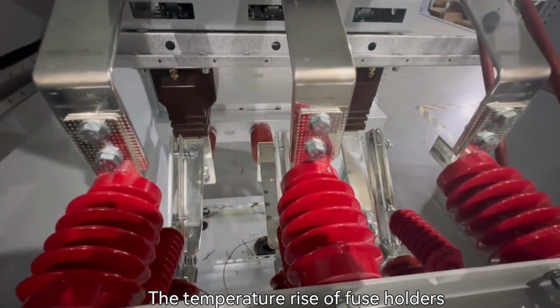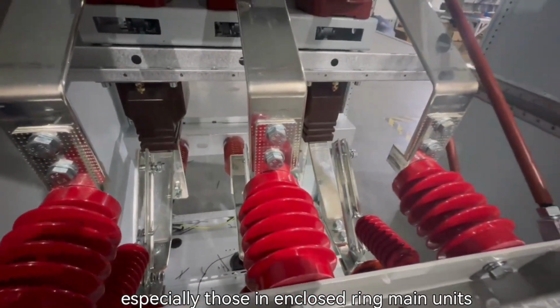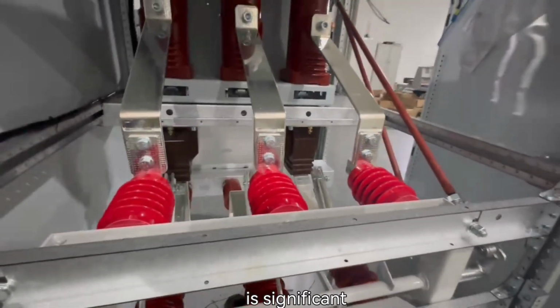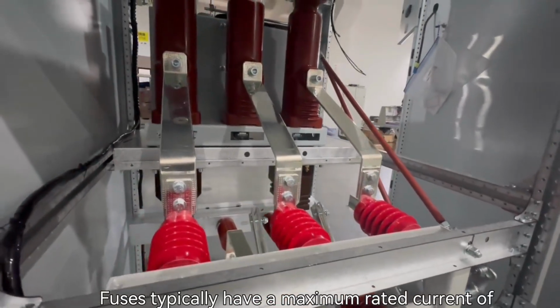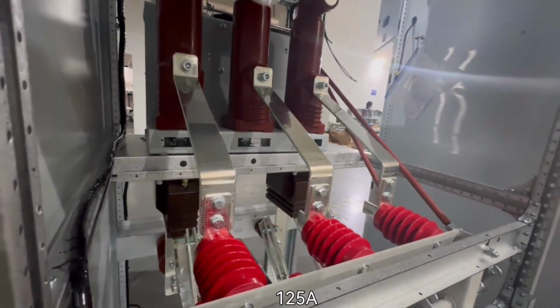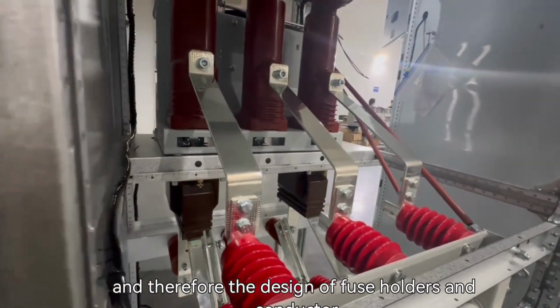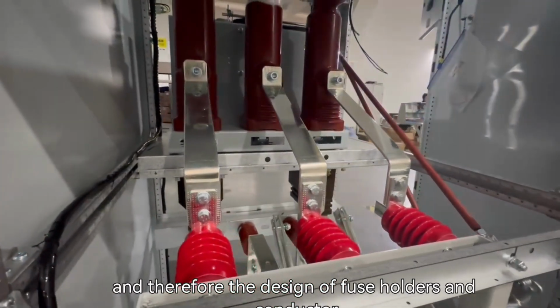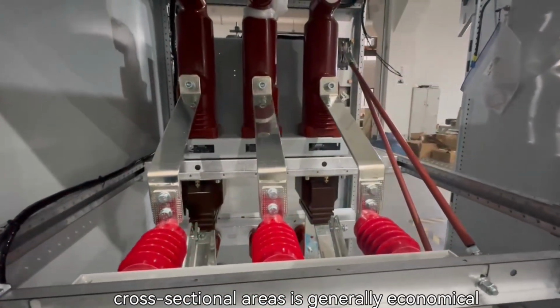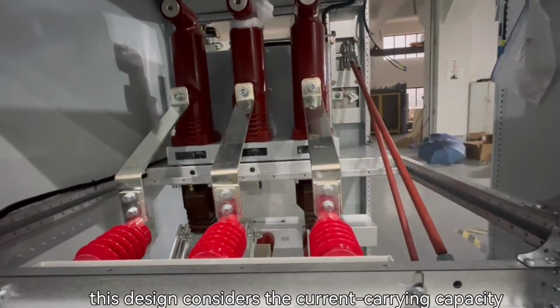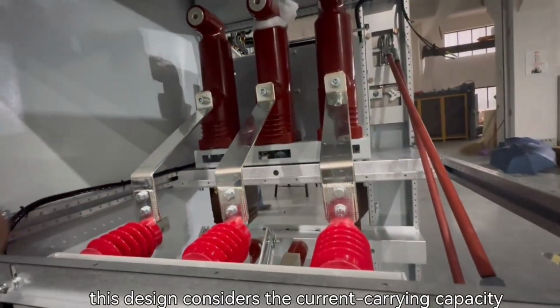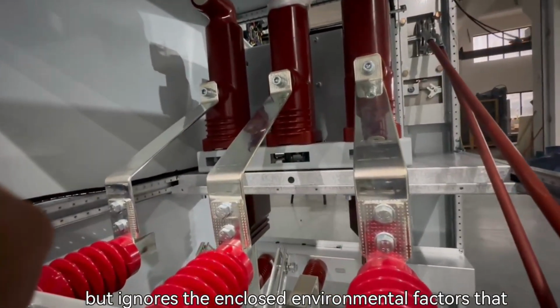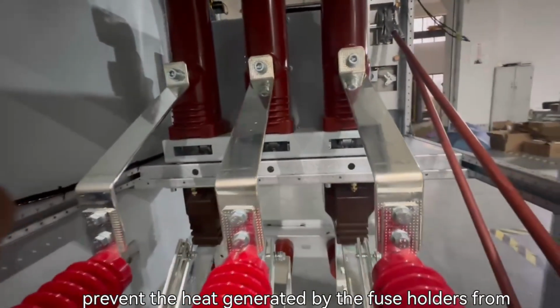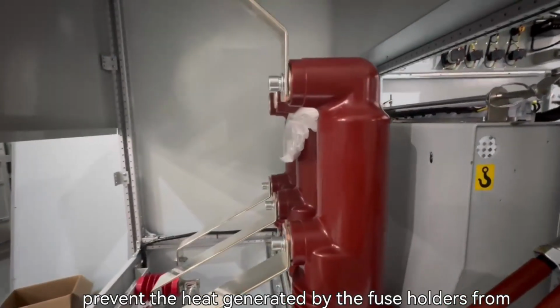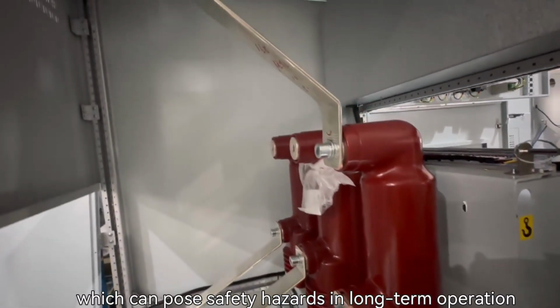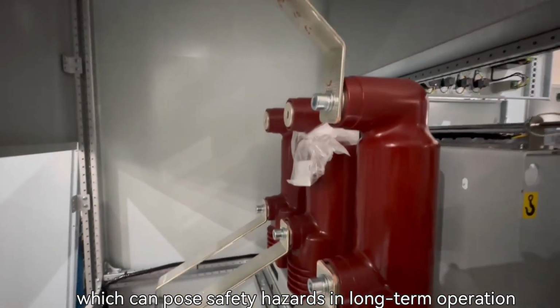The temperature rise of fuse holders, especially those in enclosed ring main units, is significant. Fuses typically have a maximum rated current of 125 A, and therefore the design of fuse holders and conductor cross-sectional areas is generally economical. However, this design considers the current carrying capacity, but ignores the enclosed environmental factors that prevent the heat generated by the fuse holders from dissipating, which can pose safety hazards in long-term operation.